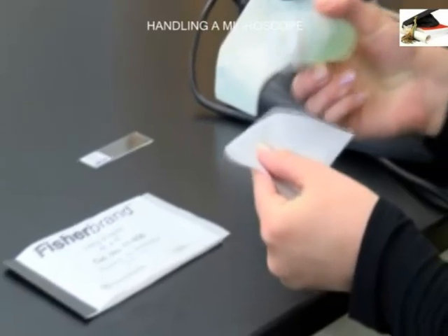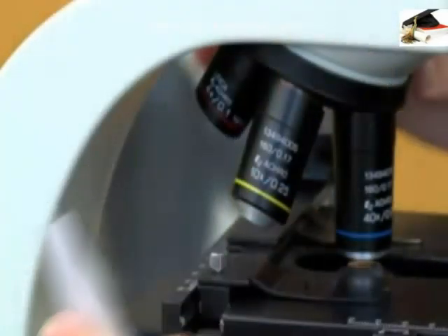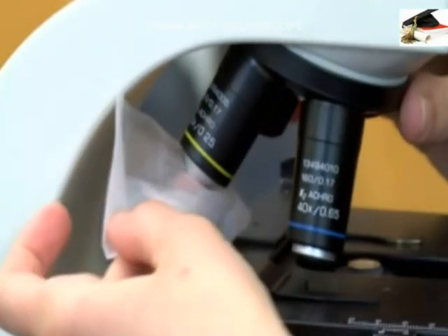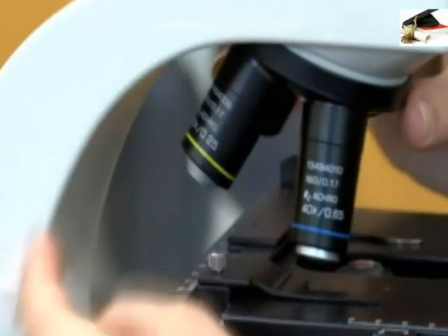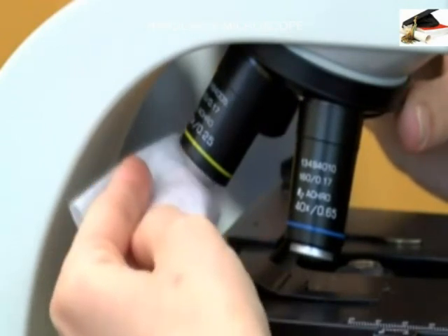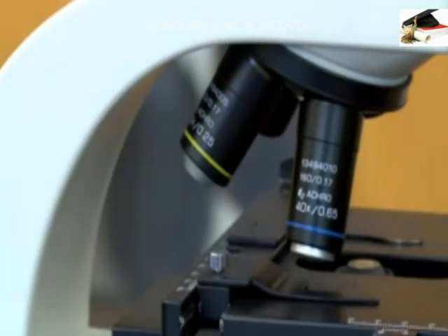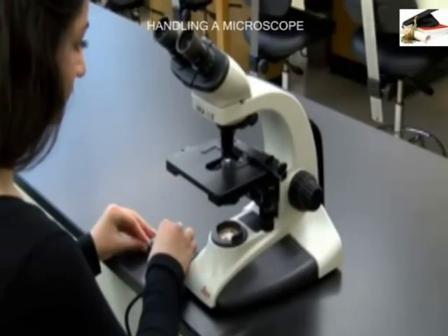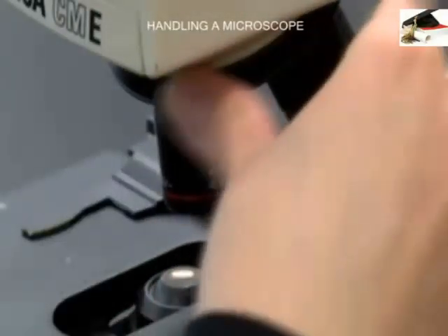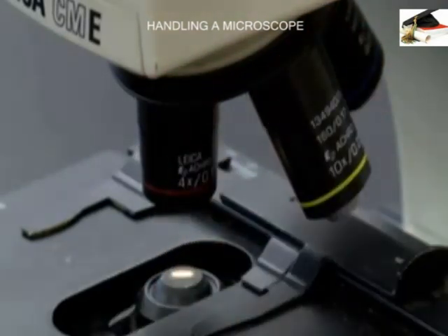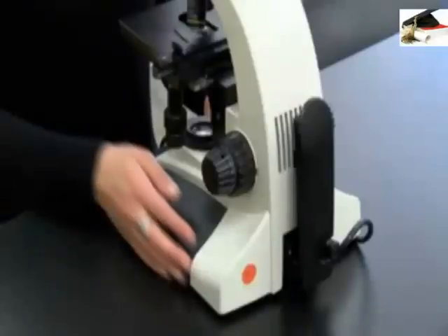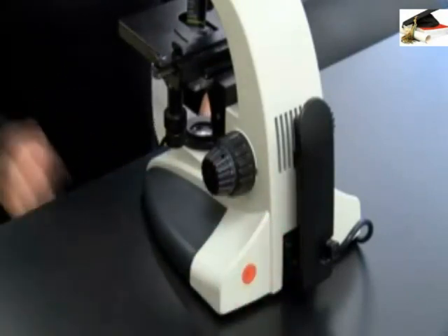Do not touch the mirror and the lenses with your fingers. Dirty lenses should be cleaned using a special soft lens tissue paper or tissue paper moistened with ethanol. Other parts of the microscope may be cleaned using a soft cloth or tissue paper. Do not wet any part of the microscope and make sure the low power objective lens clicks into position in line with the eyepiece before and after use. After use, always clean and store the microscope in a safe place free from moisture and dust.